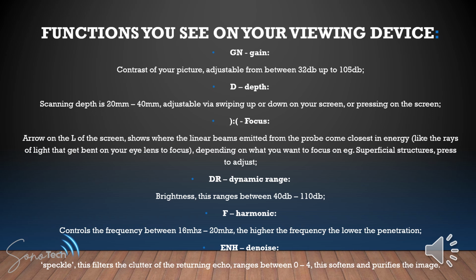Your DR standing for your dynamic range. This is where your GN or your gain is your contrast, this is now your brightness. This also ranges between 40 decibels all the way up to 110, which you can then adjust or change. Your F is your harmonic. This controls a frequency, anything between 16 and 20 megahertz. The higher the frequency, the lower the penetration. Your ENH is something called the denoise or the speckle. This filters the clutter from the returning echo.